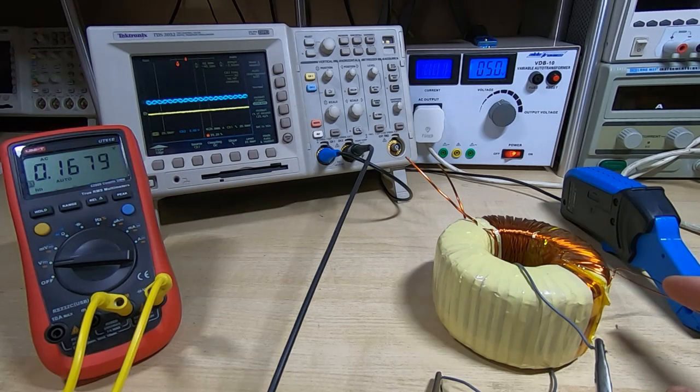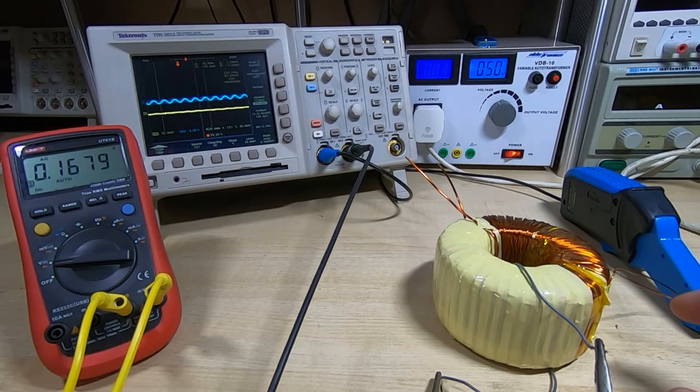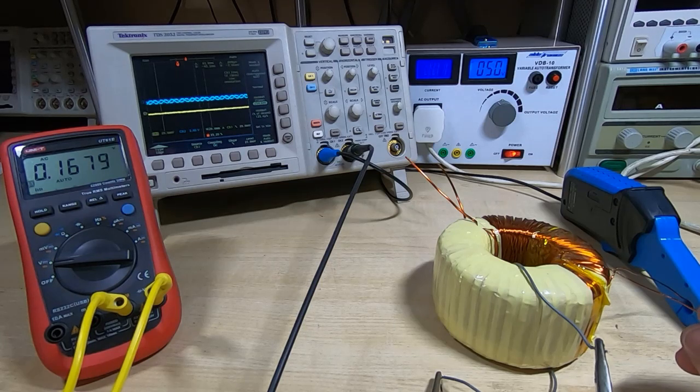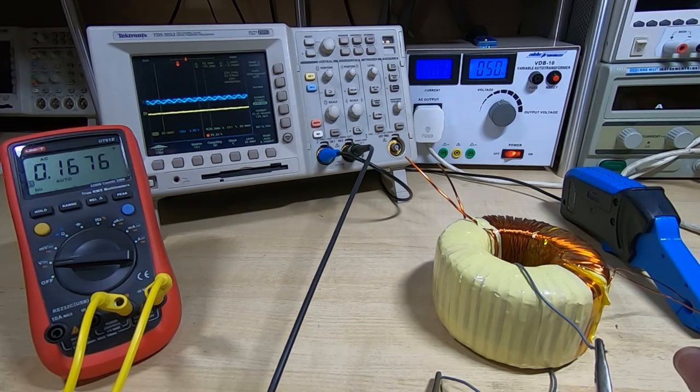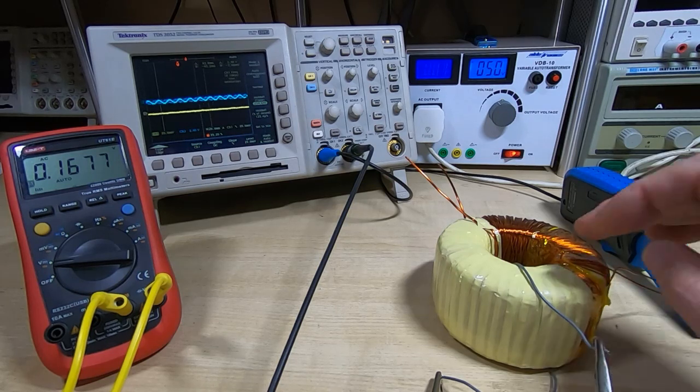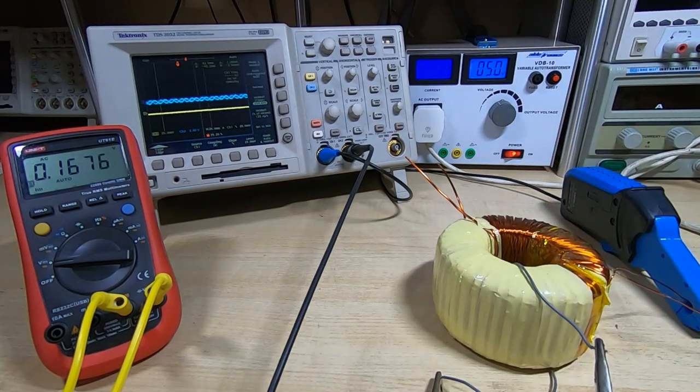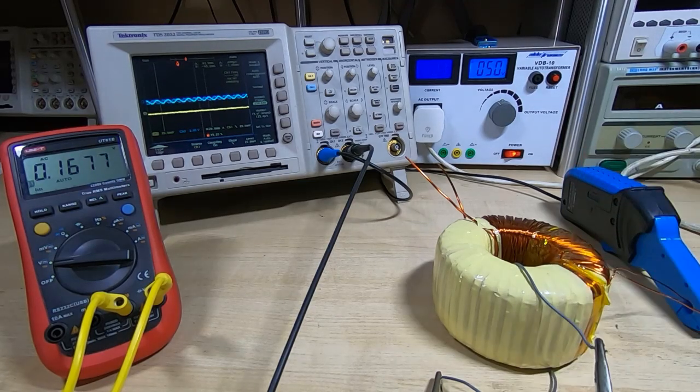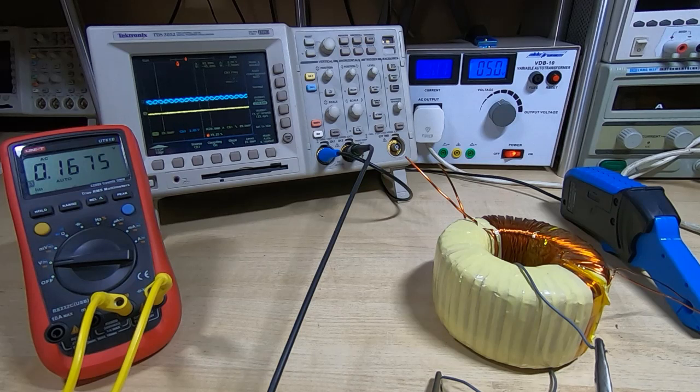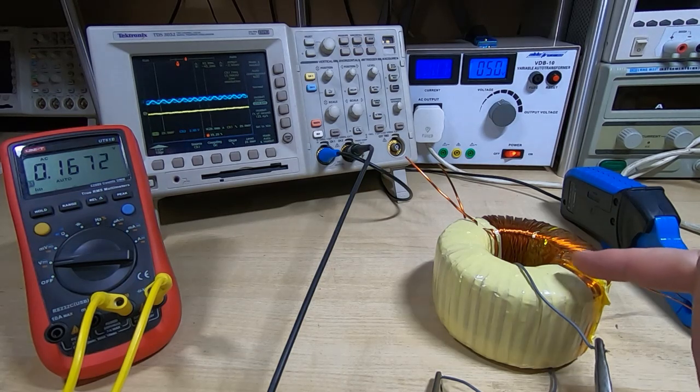We can measure the thickness of the wire and that will enable us to work out the maximum current that this winding can carry. What you then have to do is start looking at the core itself. If you measure the core and you know the material, you can work out the power handling capacity of the core. This only tells us the number of turns on the primary, it doesn't tell us what the voltage is that it's designed to run at. This will be determined to a large degree by the core.